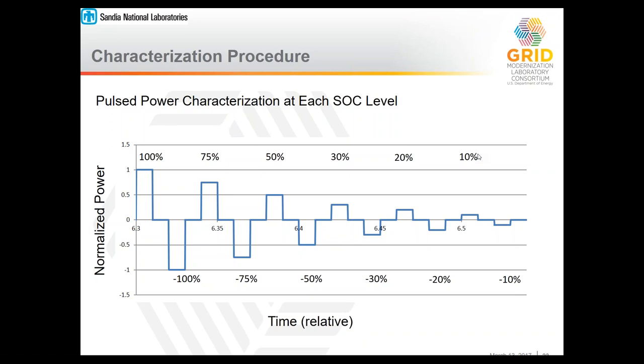Essentially what this does is it allows us to verify and build an inverter conversion efficiency model based on the specific state of charge that this test is run at. Essentially, the inverter efficiency is dependent on DC voltage, so as the battery is discharged from full to empty, you can see that the inverters become slightly less efficient, and we can incorporate that into our model using this test.